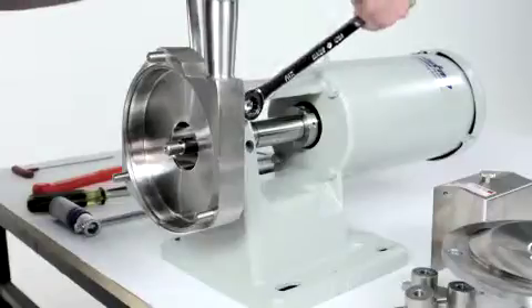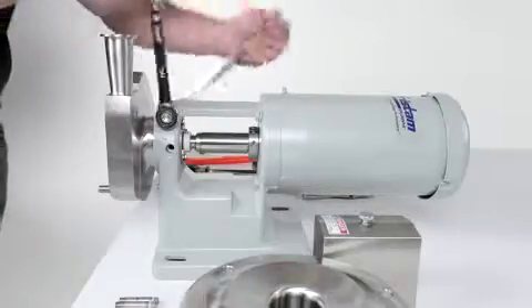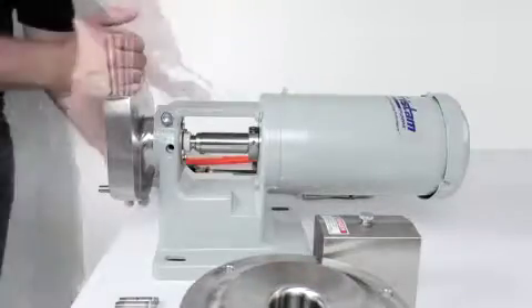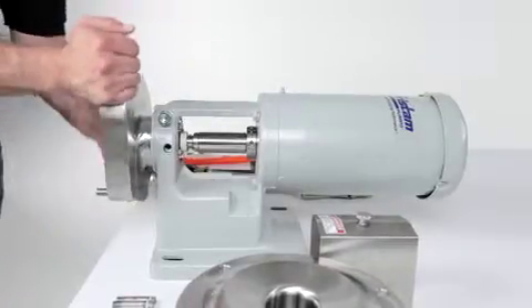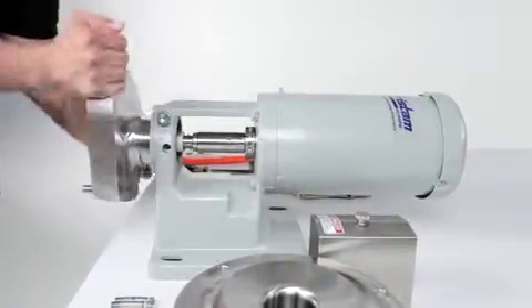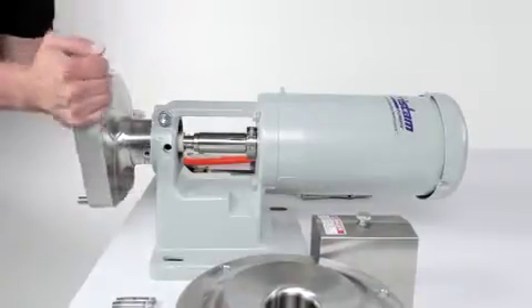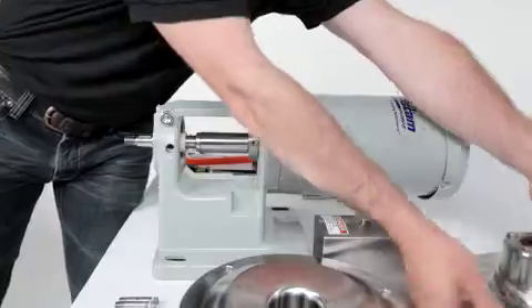Loosen the housing clamping bolt with 2 wrenches until it is loose in the flange support. Note, the clamping bolt does not have to be removed. Slide the pump housing off of the end of the pump shaft. Place the pump housing face down on the housing studs.